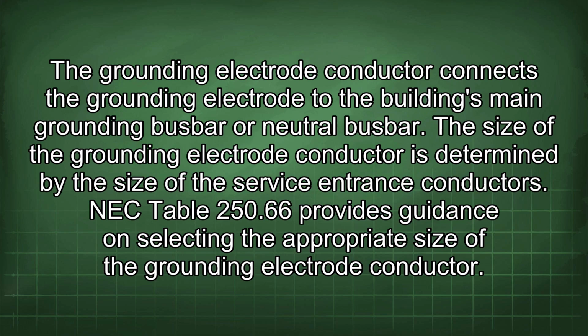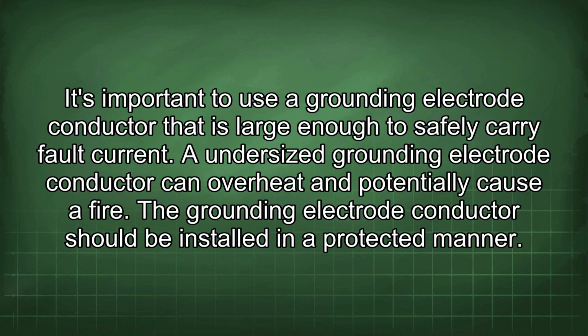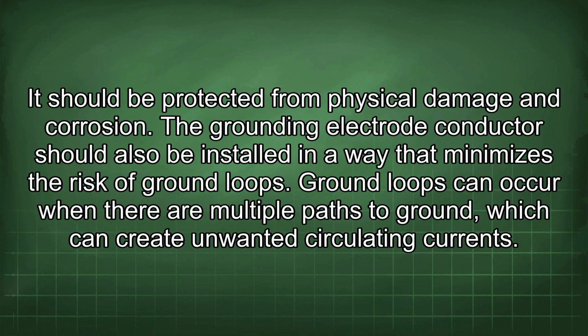NEC Table 250.66 provides guidance on selecting the appropriate size of the grounding electrode conductor. It is important to use a grounding electrode conductor that is large enough to safely carry fault current. An undersized grounding electrode conductor can overheat and potentially cause a fire. The grounding electrode conductor should be installed in a protected manner. It should be protected from physical damage and corrosion.